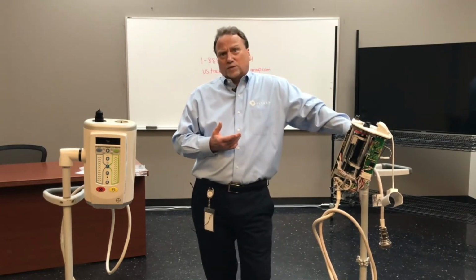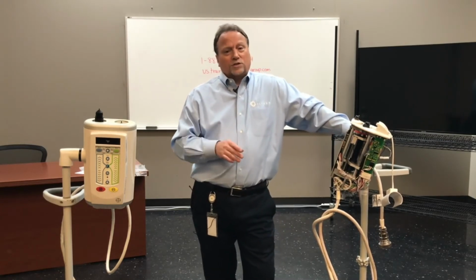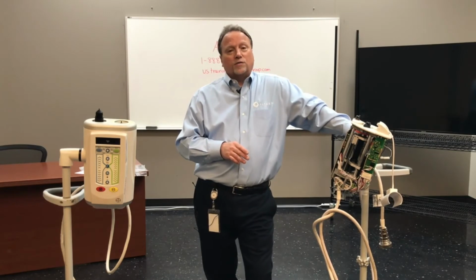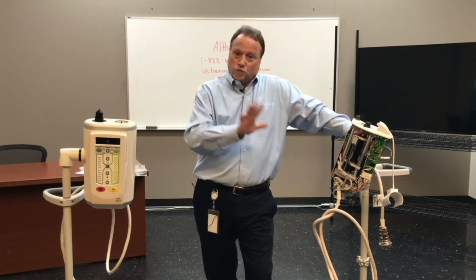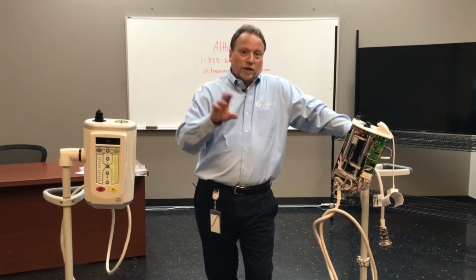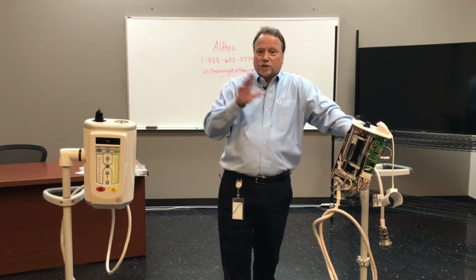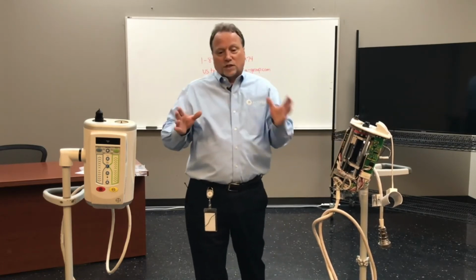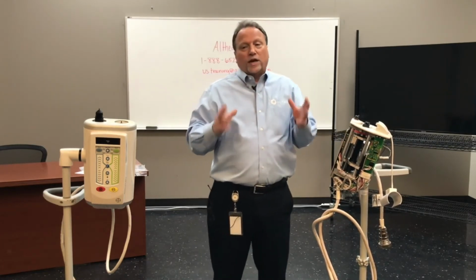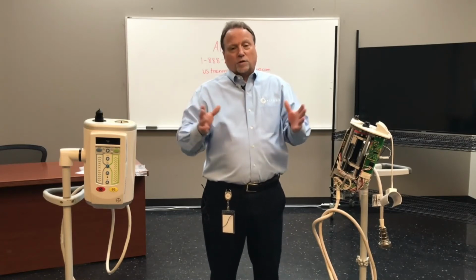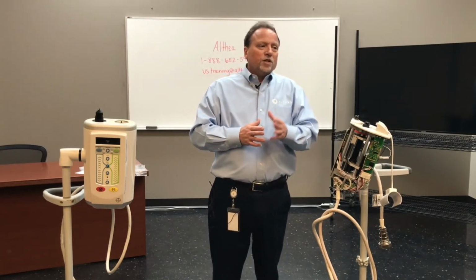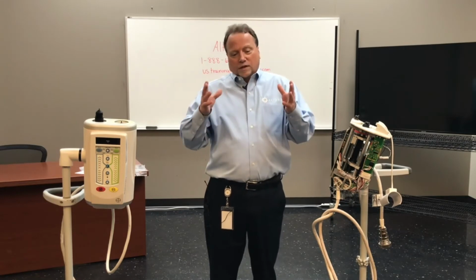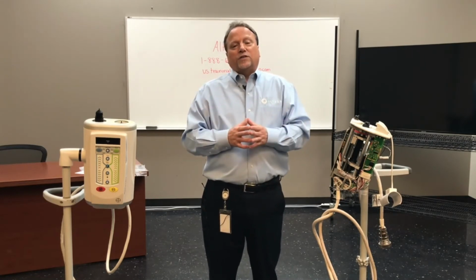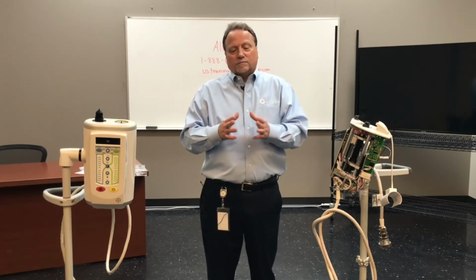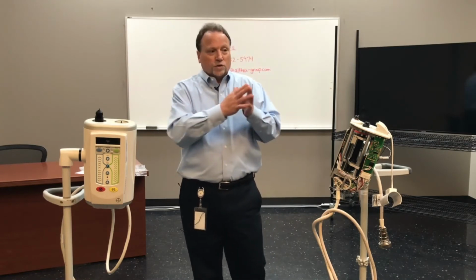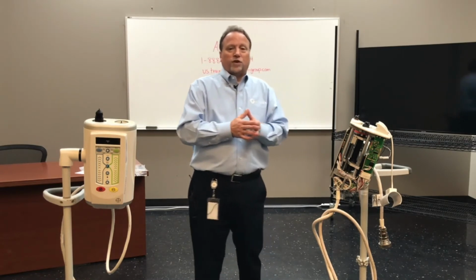With a few exceptions, like the Empower MR, that's just a rare bird all by itself, and it's hydraulic driven, so we stay away from that. We'll let the OEM handle that. But all the other injectors out there, the service kit that we have put together will handle the injectors that you're going to come across. So pressure verification, that service kit is going to handle that information, so you can handle any injector to do the test that you need for pressure verification.